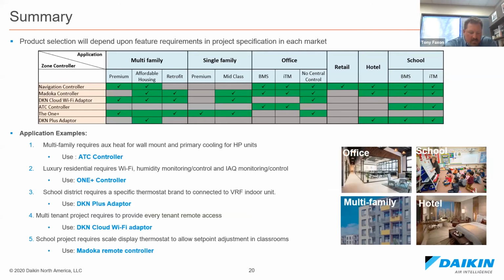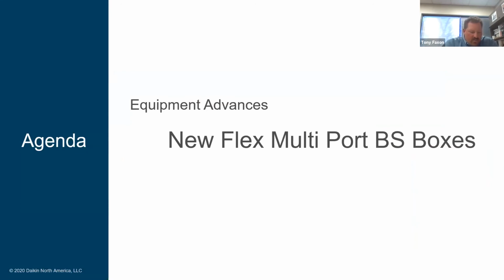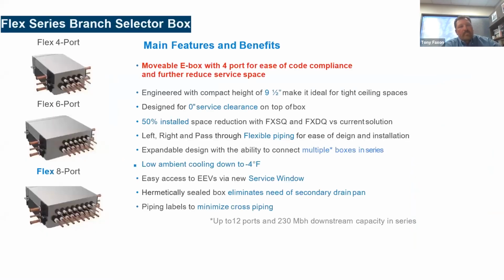While I still have a few minutes left, I'd like to mention a new advancement in the VRF family, the new multi-port flex boxes. The Flex Series branch selector box. Since the first system that had the ability to simultaneously heat and cool was invented by Daikin back in the early 90s, heat recovery has grown to be a significant portion of the VRF market, and it's dominant in the United States. The original BS boxes have grown in technological steps from simple reversing valves in a box to a little bit more noisy solenoid valve combination, and then nowadays to the quieter combination of electronic expansion valves. You've got single port, you've got multi-port, and we're now seeing the next step in that evolution. Daikin's new Flex multi-port boxes.